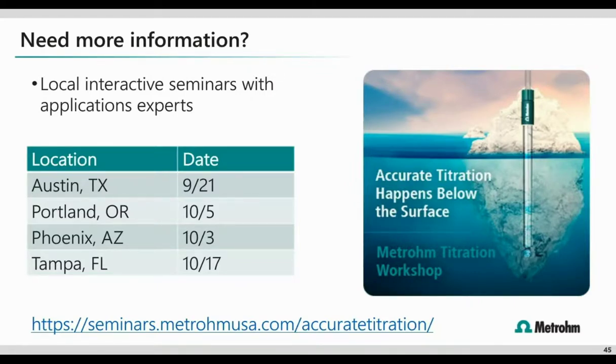Yes, thank you. Now, the next question asks, do both the tip and diaphragm need to be submerged in the sample to get an effective reading, or just the tip? We recommend that you have the tip and the diaphragm submerged in your buffer or sample at the time of measurement. So the answer is yes, the diaphragm and the bulb.